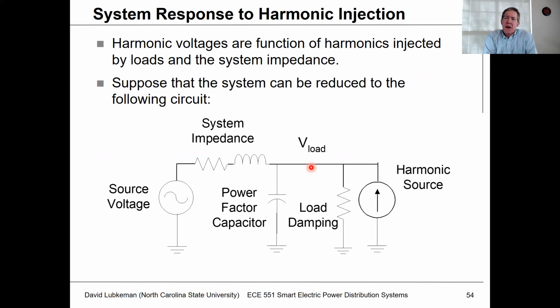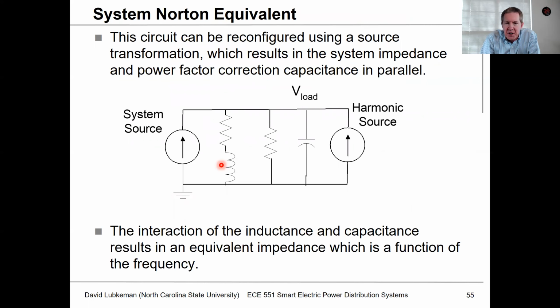So when we're talking about the impact on the system, the other thing we have to worry about is how does the system impedance change with frequency? Before, we didn't have to be concerned about this because we were just working with 60 hertz, but let's suppose that we have this as an equivalent model for the power system. We have a source, we have a system series impedance, then I have a power factor correction capacitor in here. And then I might also have some load damping as well. So what's going to happen if I have a harmonic source? Well, one thing we can do to make this a little clearer is take this Thevenin equivalent for the circuit and convert it to a Norton equivalent.